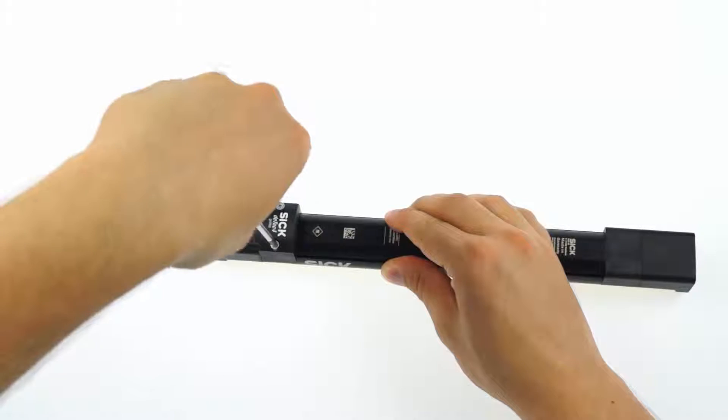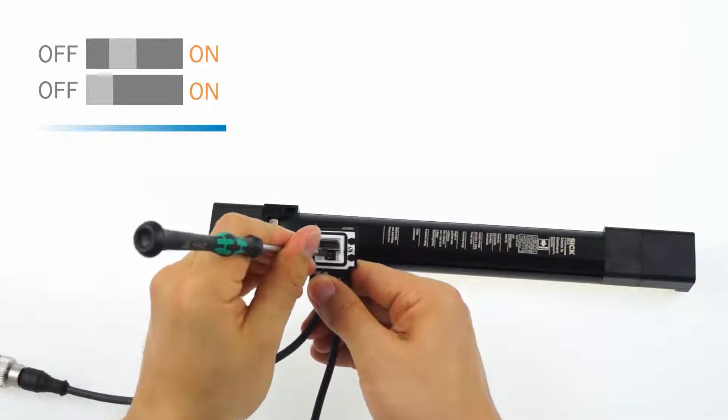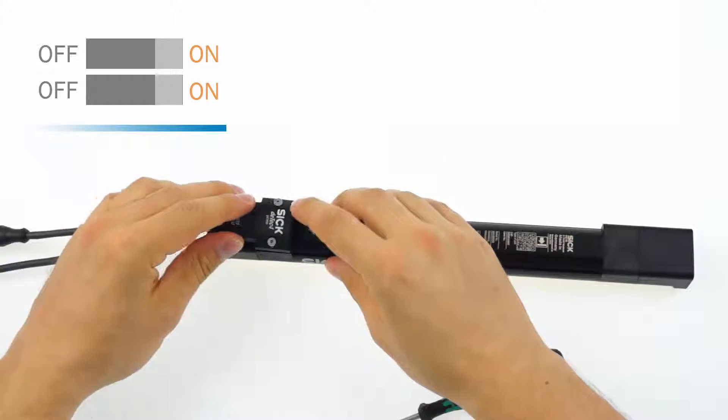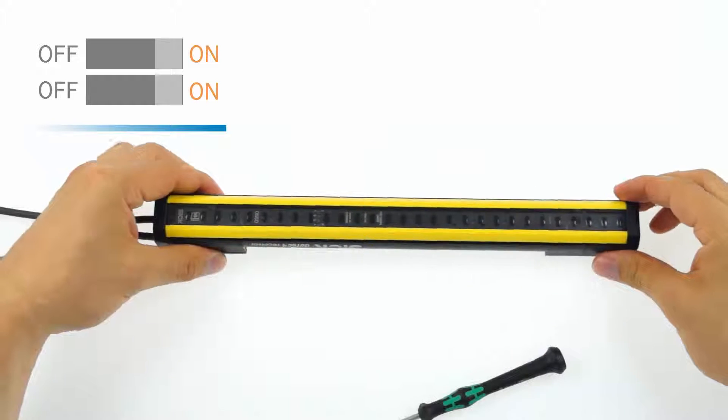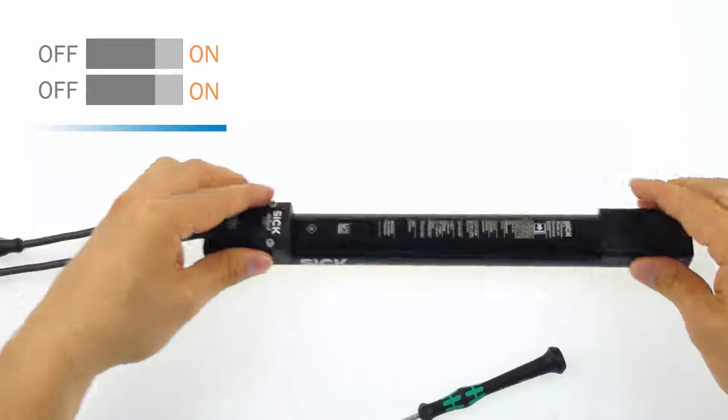In the first step detach the system plug. Set both of the DIP switches to ON and put the plug back on the device. Switch on the power. The field LEDs are flashing green and yellow now. Disconnect the device from the power supply within 10 seconds.